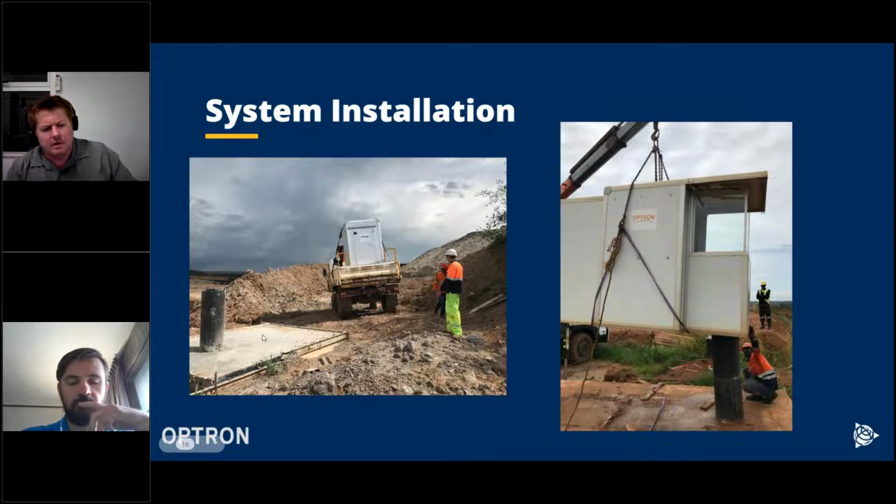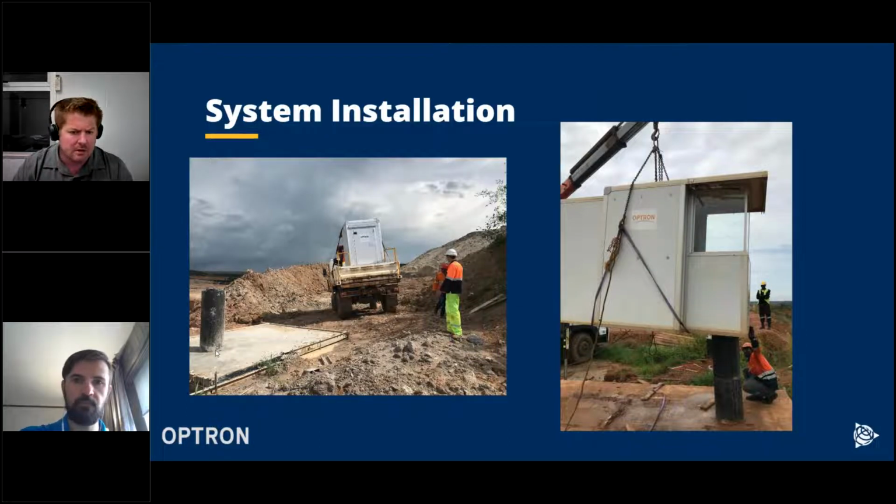What we also do offer is a steel pillar with quite a wide base that we can mount to a concrete slab, and then we fill up that beacon with soilcrete, so a mix of sand and cement. We also find that is quite stable, and it makes the installation much faster as well, because you don't really have to worry about, like in this case, you can just place the cabinet and position it correctly, and then you mount the pillar from the inside.